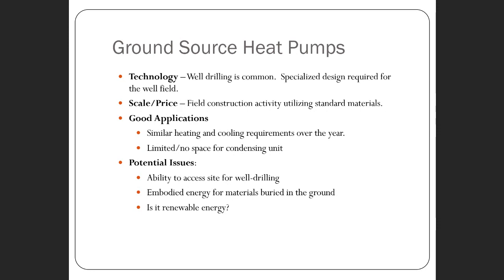Good applications for ground source heat pumps are where we have similar heating and cooling requirements over the year. In the case of a commercial building like this one, we heat part of the year and air condition part of the year, which works out well for a geothermal system. Another good application here was that we didn't have a good place to put a cooling tower or condensing unit to reject heat from an air conditioning system.